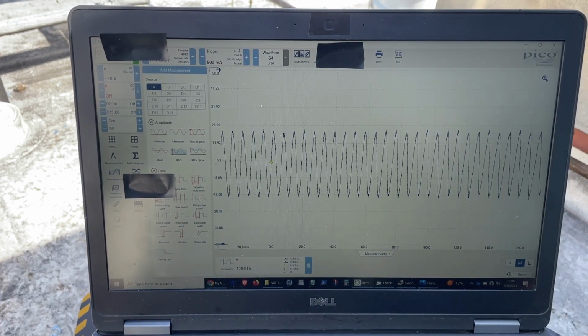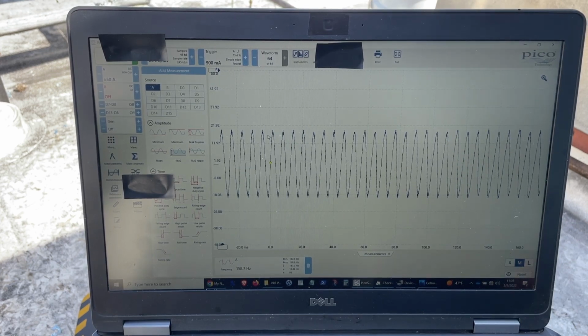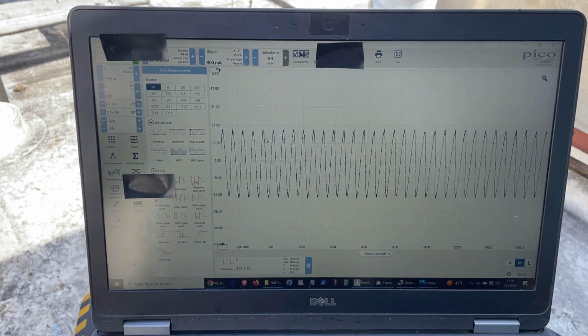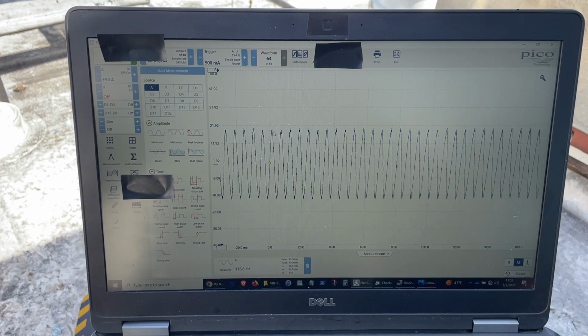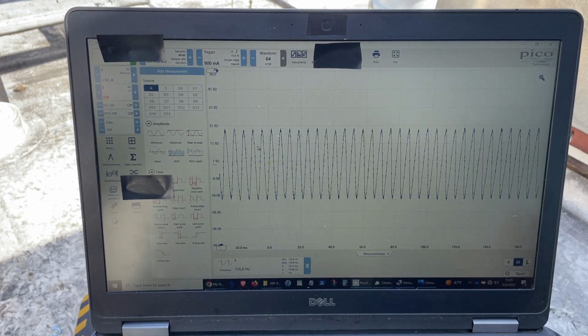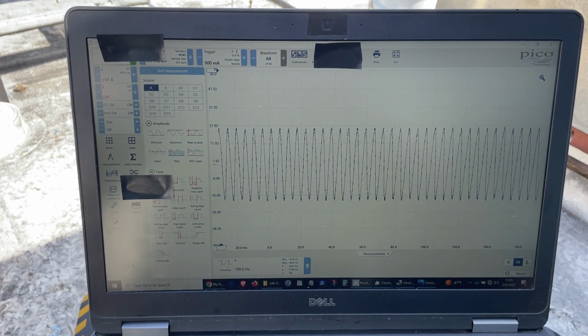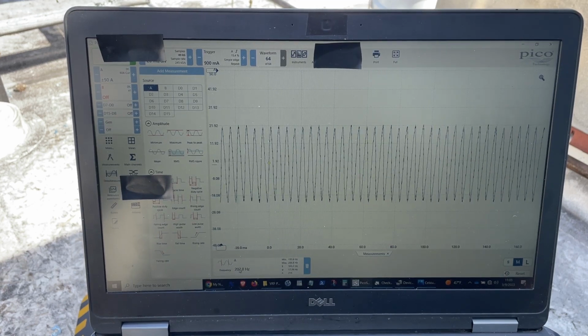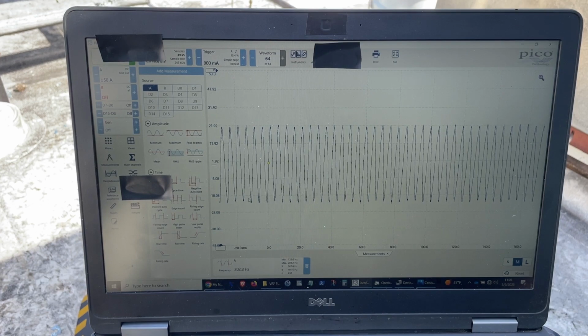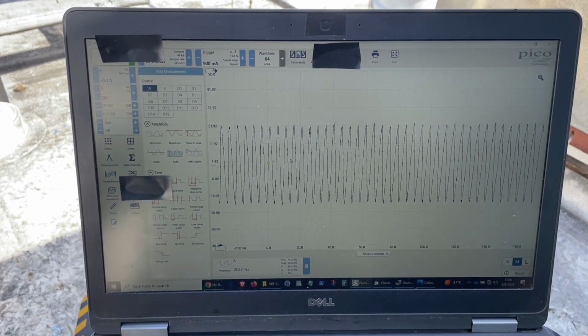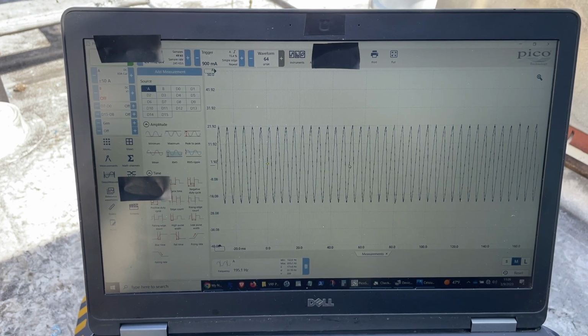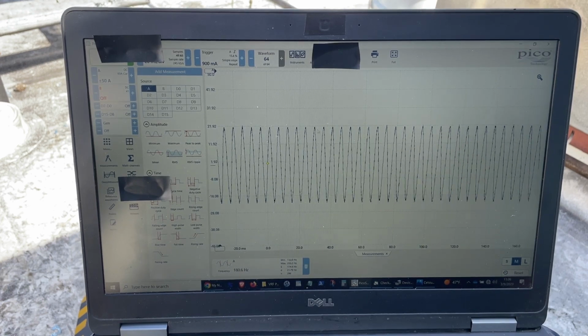The interesting thing about an inverter compressor is you might think it's running on some weird waveform or DC, because the boards do produce DC, but it's not. It's AC. The boards take in mains, convert that to DC, and then the board can use that DC to make very finely controllable AC frequencies. So that's all the inverter is doing, and it's running wide open now because this thing's been down and is under really high load, so it's wanting to run wide open. You can see we're kind of at maximum amps here.